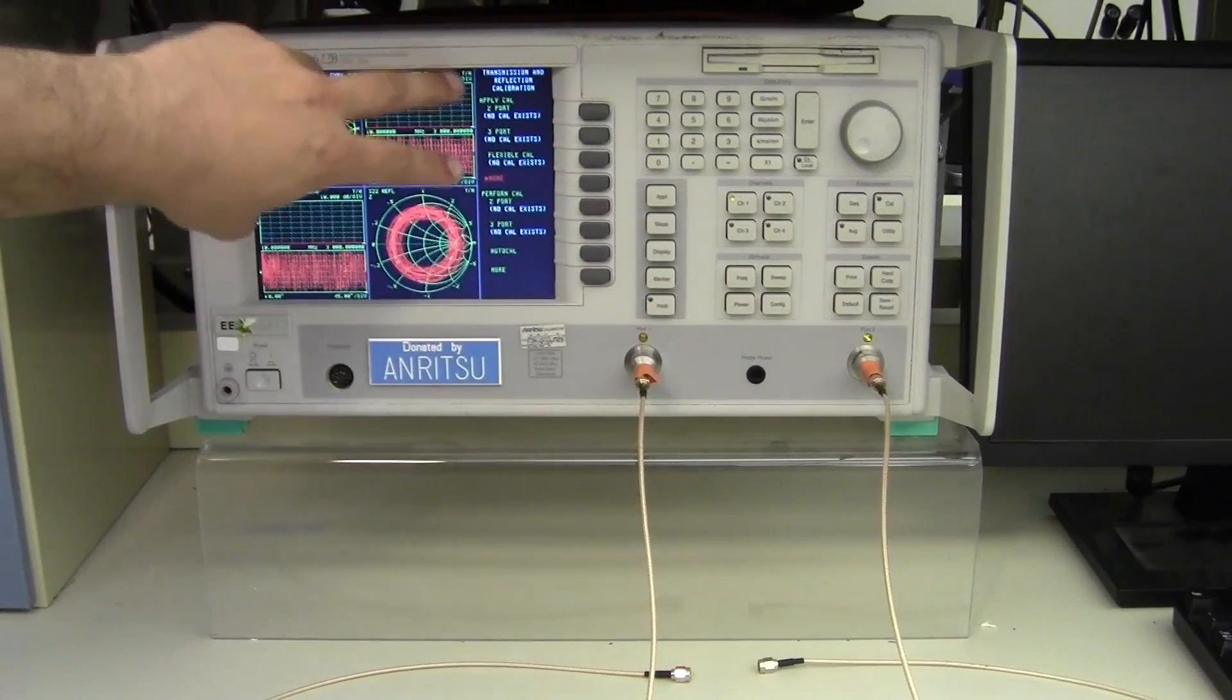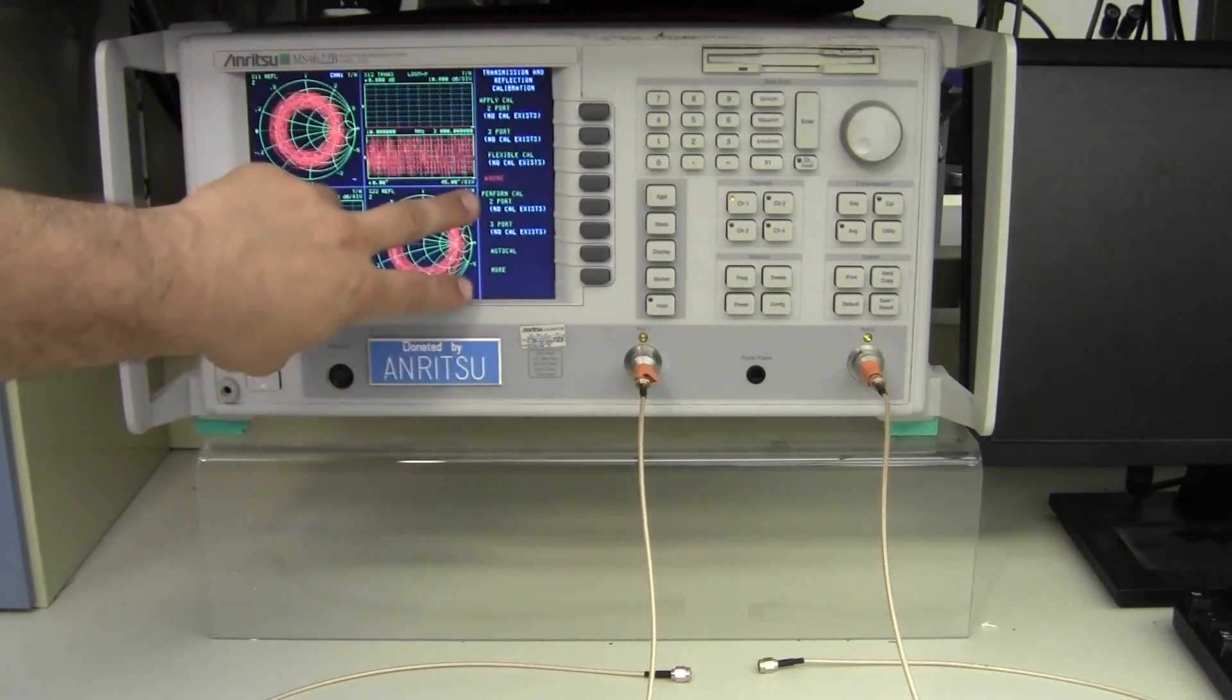Then to begin the calibration, I will on the far right press the calibration button. It asks me if I would like to apply one of the calibrations that already exists or perform a calibration.